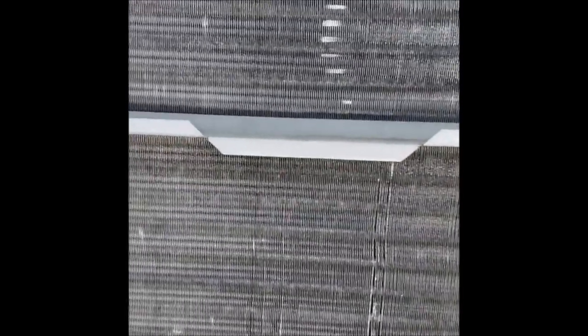I did use a little bit of condenser coil cleaner just to see if that would take it off better, and it really didn't do anything else. So the Viper coil cleaner did its job, did it just as well as condenser coil cleaner would, and definitely highly recommend it. Looking forward to using it more often for these evap coils.